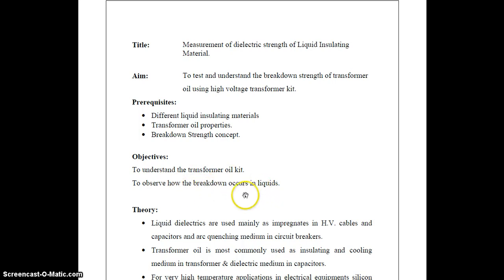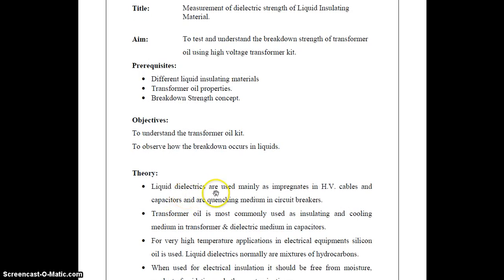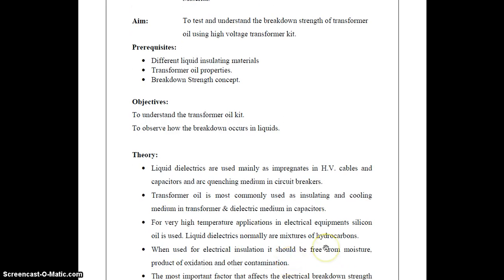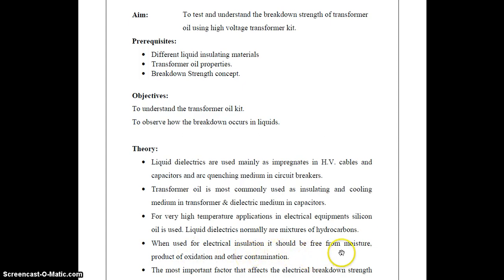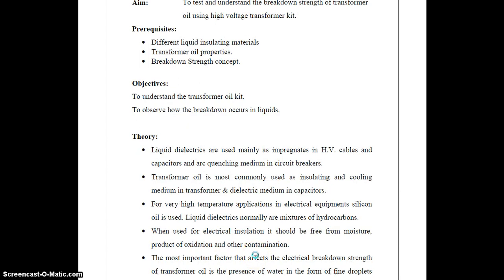Theory. Liquid dielectrics are used mainly as impregnates in high voltage cable, and also in capacitors and as an arc quenching medium in circuit breakers. Transformer oil is most commonly used for its insulating and cooling properties in transformers and as a dielectric medium in capacitors. For very high temperature applications in electrical equipment, silicon oil is used, and liquid dielectrics are normally a mixture of hydrocarbons. When used for electrical insulation, it should be free from moisture, products of oxidation and other contamination.